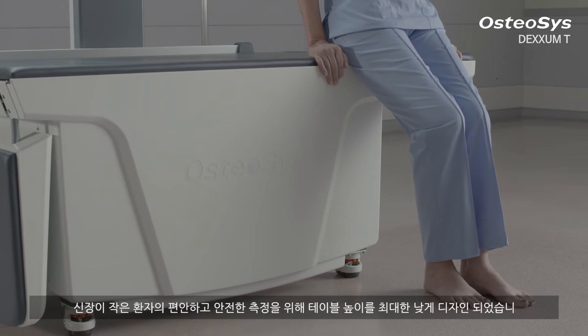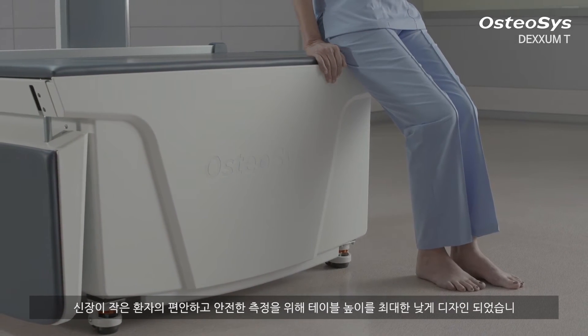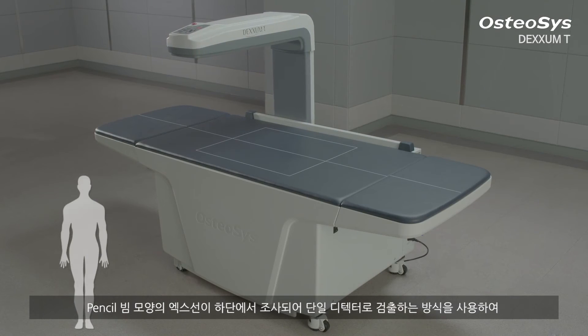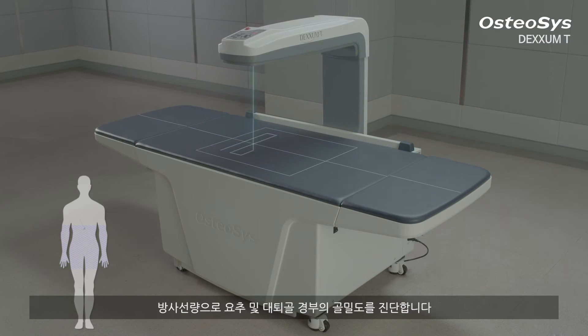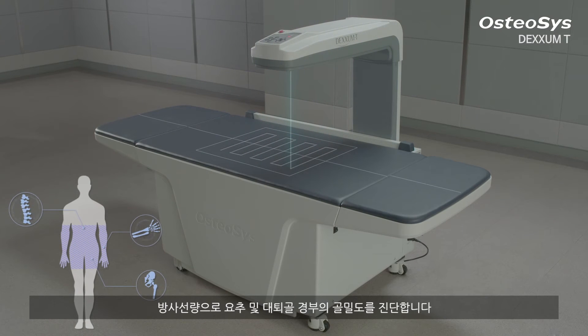We lowered the height of the table as much as possible for the safety and relaxation of senior patients and those with relatively low heights. By using DEXXUM T's single detector with a pencil shape X-ray beam source, you can diagnose the BMD of AP spine and femur with a low level of radiation.